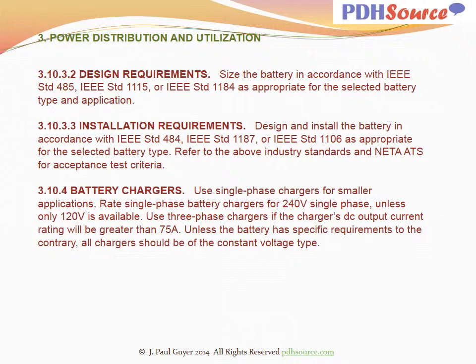For battery chargers, use single-phase chargers for smaller applications. Rate single-phase battery chargers for 240 volts single-phase unless only 120 volt is available. Use three-phase chargers if the charger's DC output current rating will be greater than 75 amps. Unless the battery has specific requirements to the contrary, all chargers shall be of the constant voltage type.